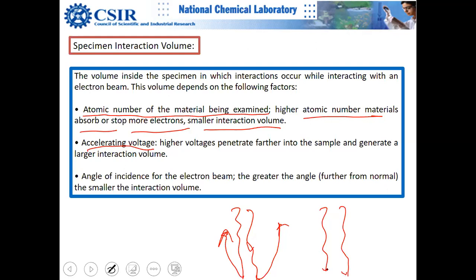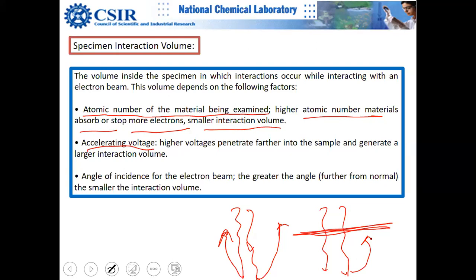High energy electrons can penetrate deeper, but secondary electrons generated deep inside may not have sufficient energy to escape the surface. The angle of incidence also matters a lot; you can easily tilt the stage in SEM to change the angle of incidence.